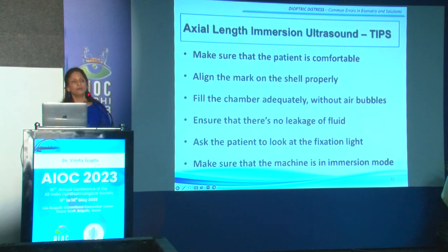And while doing immersion biometry, remember that the patient should be comfortable. So you can either keep the patient supine or even in the reclining position. Align the mark on the shell properly with the probe inside, which is submerged in the water bath there. Fill the chamber adequately without any air bubbles. That is important. Ensure that there's no leakage, so overflow should not be there. Ask again for the patient to look into the fixation light. That's important to ensure that the alignment is being done in the axial direction, and make sure that the machine is in immersion mode.